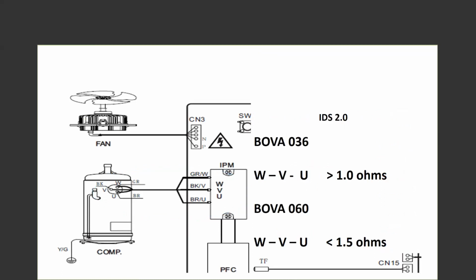So on the 2.0 unit, the 3-ton is going to ohm out basically greater than 1 ohm. And the 5-ton is going to ohm out... all three of those are going to be the same. It's ohming out like a 3-phase compressor. And those are going to ohm out less than 1.5 ohms.